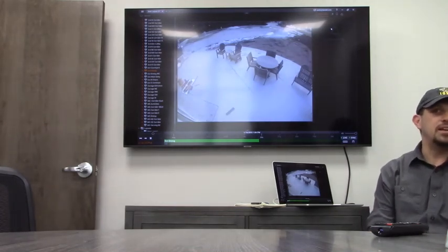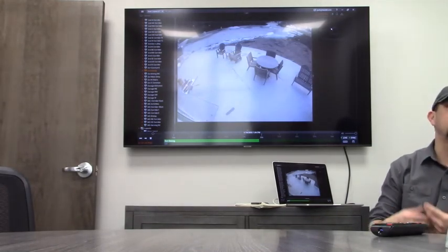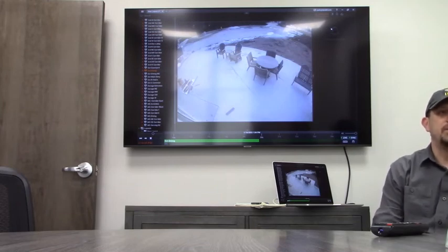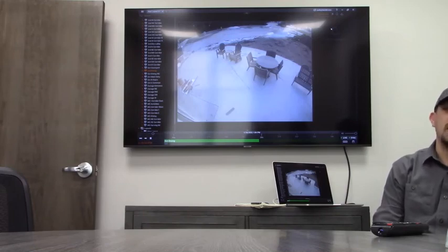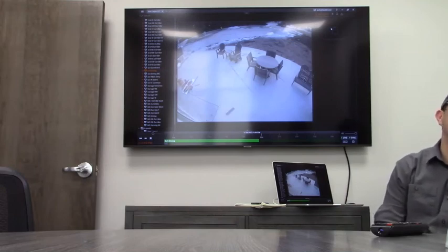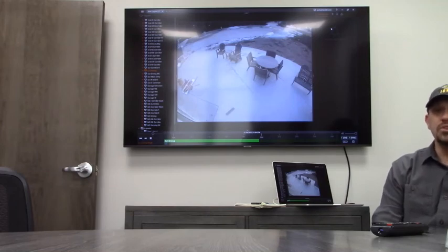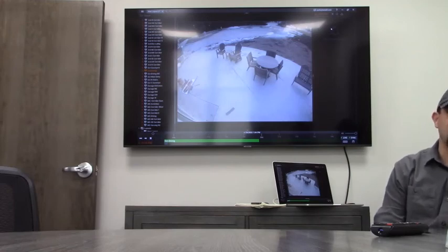I believe we did get generator circuits up there for the network equipment though, which would include the NVR and all your switches and internet service and all that. Because that stuff's a lot harder to keep on a substantial battery. You can put a big UPS in, it might last an hour. Our batteries are all sized to last a minimum of 24 hours for access control, card access and fire alarm. Which is vital in a facility with mag locks as door security, because without power, they're not locked.